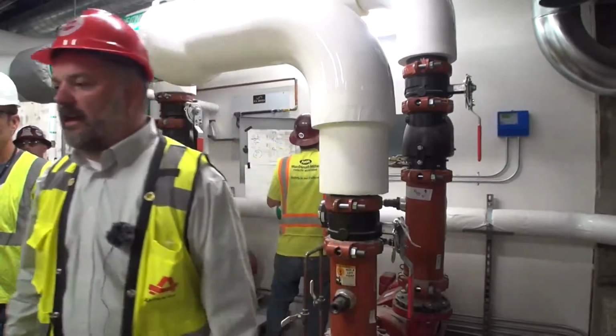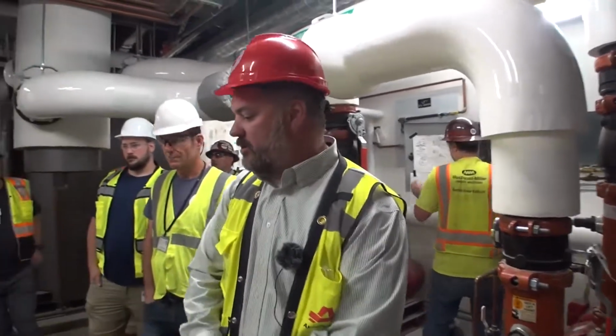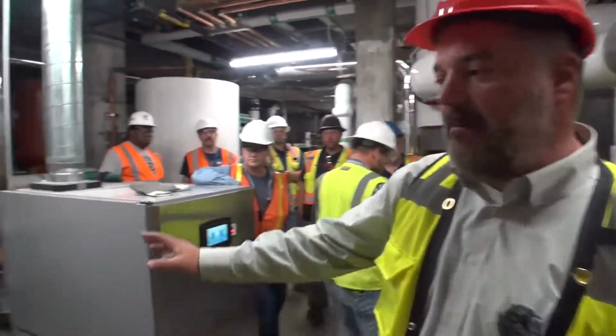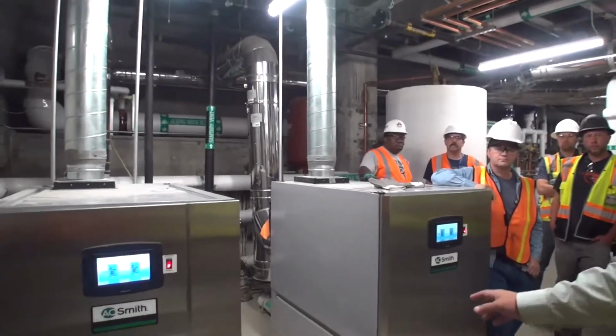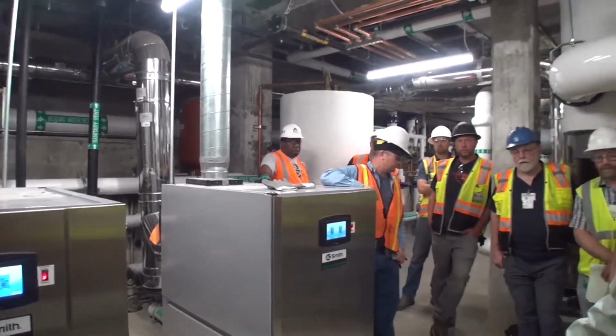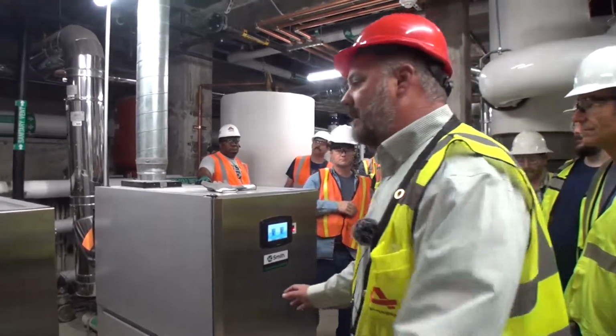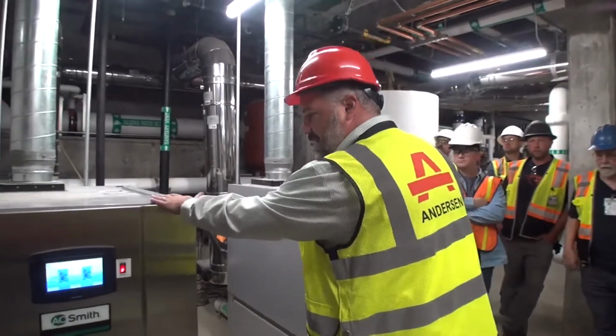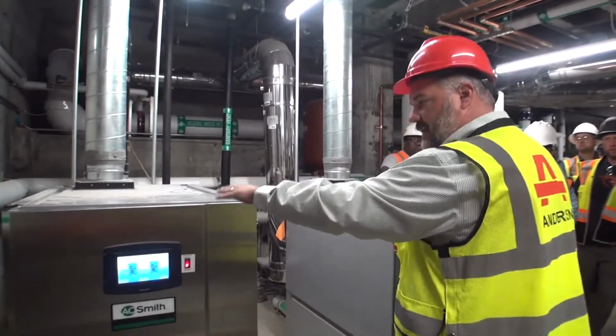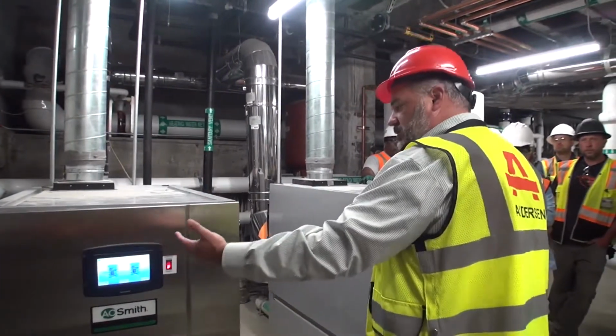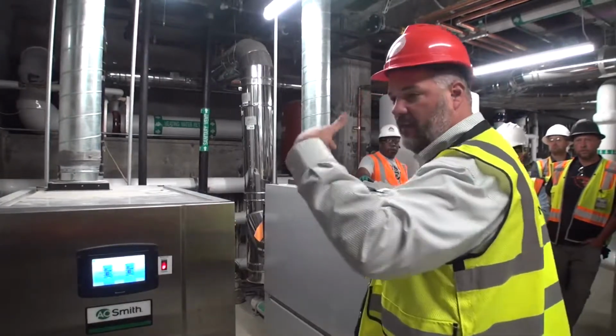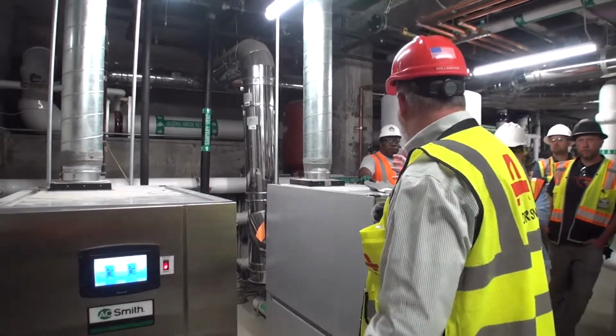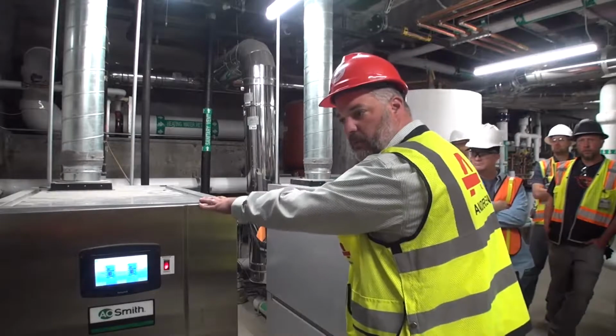So first things first, we have 2 XW1300s. What that means is each one of these boilers is 1.3 million BTUs. They're set to a lead lag, which means that one's going to heat, then the other's going to heat, and they're going to do that 1 stage, 2 stage, 1 stage, 2 stage, and then they'll reverse so that we're going to be able to give equal run time to both these boilers.